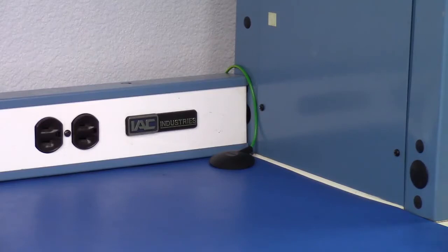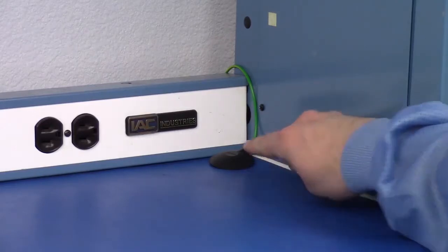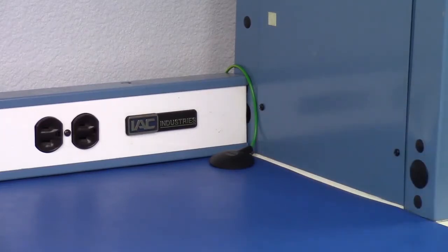It is important to note that the SCS724 Workstation Monitor only monitors the mat's connection to ground. It does not ground the mat. The mat must be grounded separately.